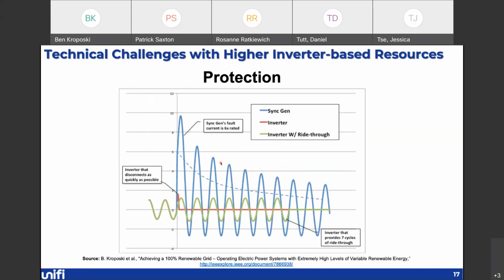Another one is protection. It sounds like at your last meeting you had people from SEL come in and talk about protection. I won't go through it in too much detail, only to say that protection of the grid is an important aspect. And what we mean by that is the ability to recognize that a fault has occurred and then to isolate that fault and then keep the remainder of the system operating properly until that fault is cleared.